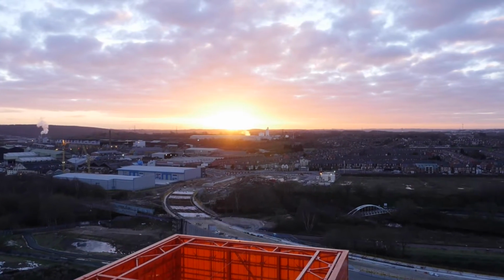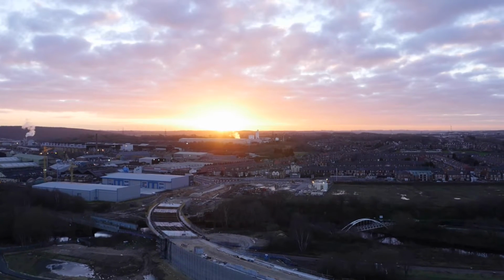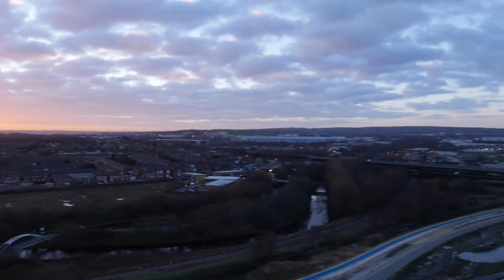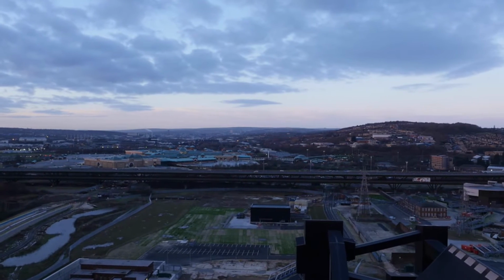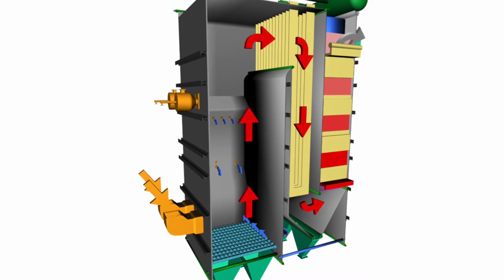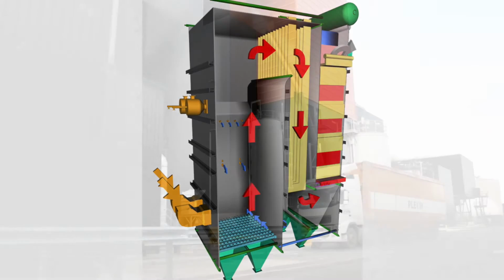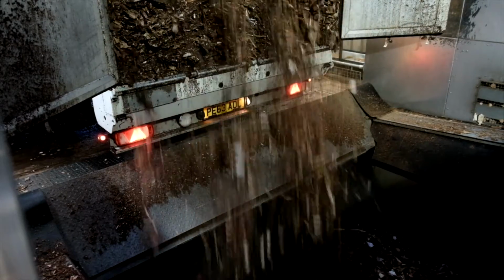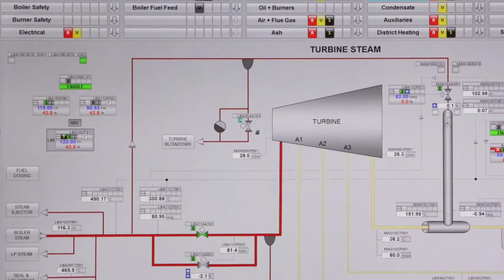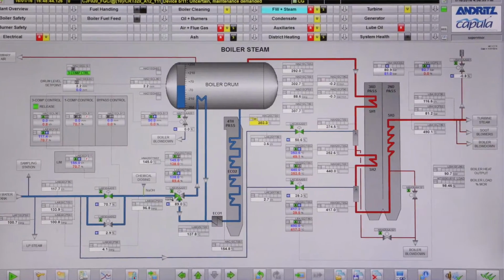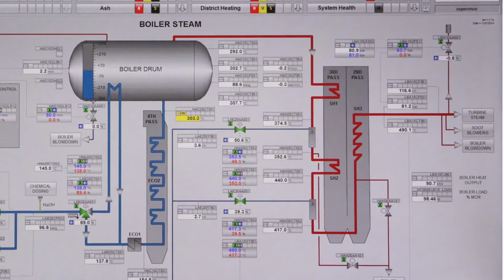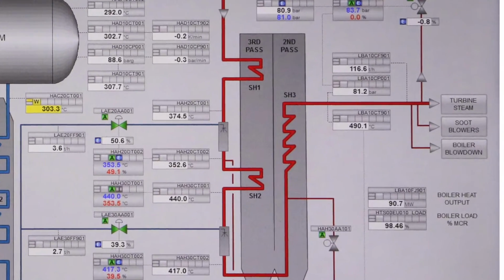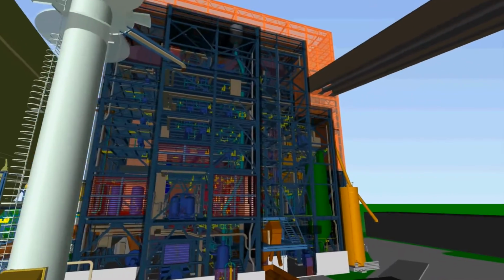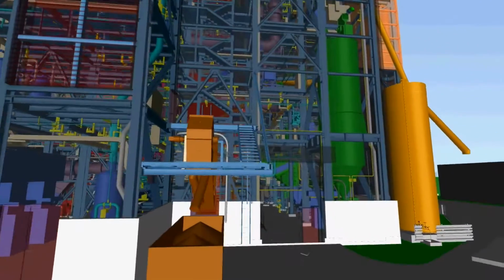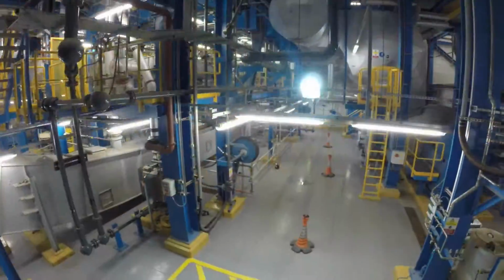Andritz's scope encompassed the electromechanical power plant equipment, except the external fuel handling, the turbine generator unit and the high-voltage part. The EcoFluid AC boiler has a design heat input of 96.9 megawatt thermal, firing recycled wood, which produces 119 tons per hour of superheated steam. The comparatively high steam parameters are 490 degrees Celsius and 83 bar gauge at the boiler exit. Firing recycled wood is achieved by following a successful design concept with superheater wings in the second boiler pass.